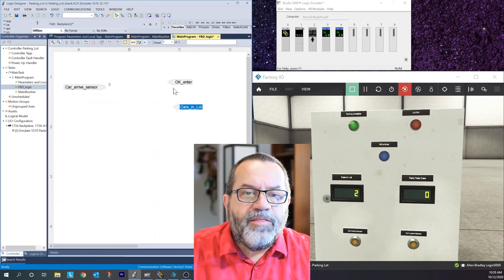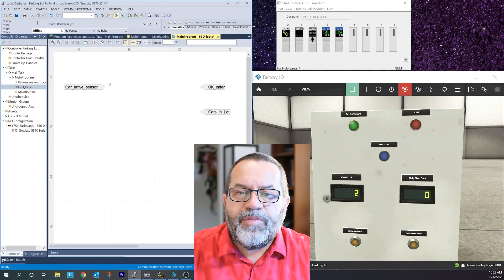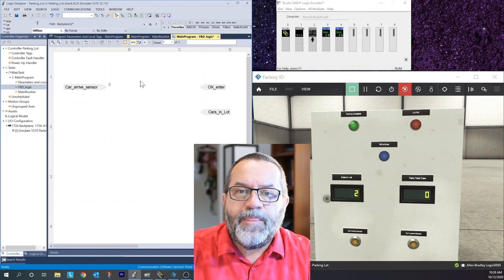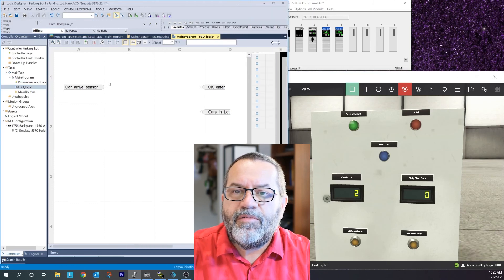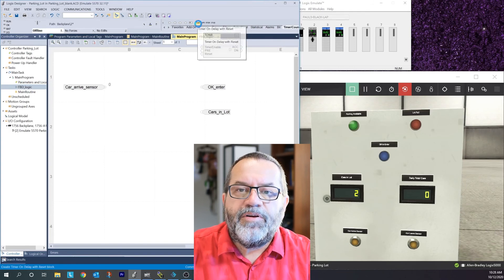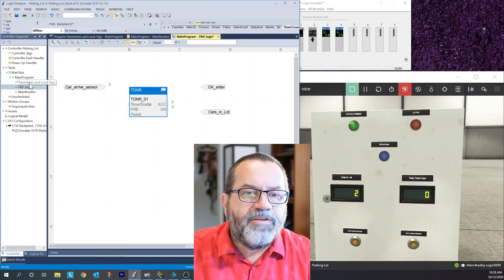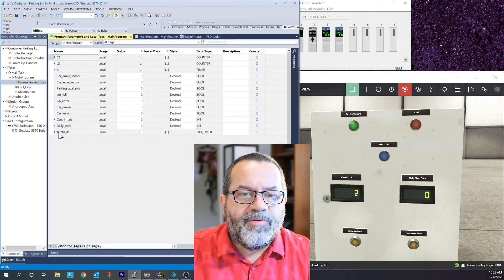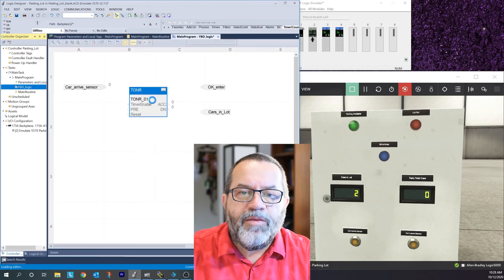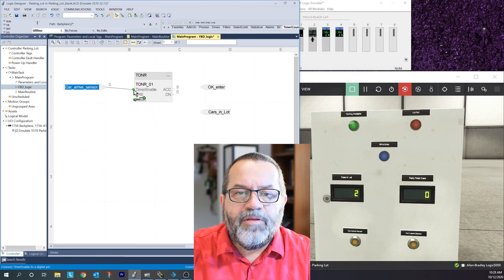The first thing I did in ladder logic was start a timer, so I'm going to do that in function block now. It's quite different - I don't have to create a tag for my timer. I just go over to timers and counters and select a TON - timer on - and put that on my sheet. When I go back to my tags, Studio 5000 created that tag for me automatically. I don't have to worry about that.